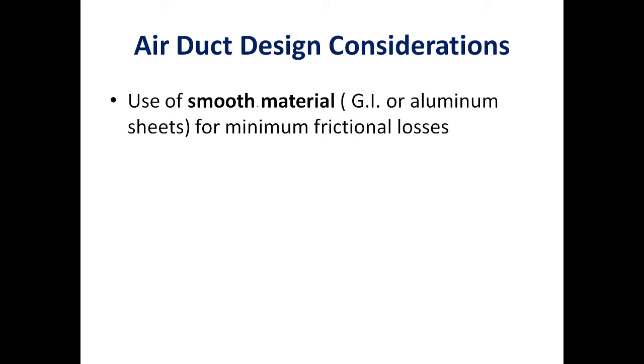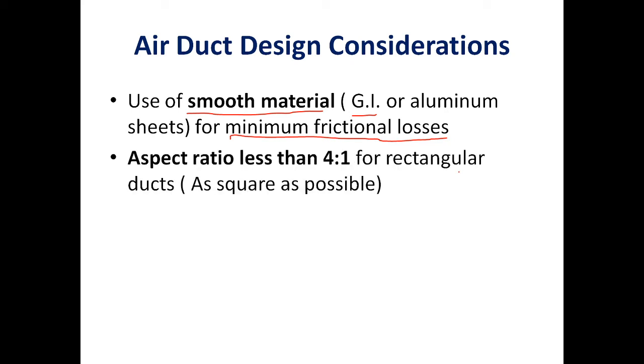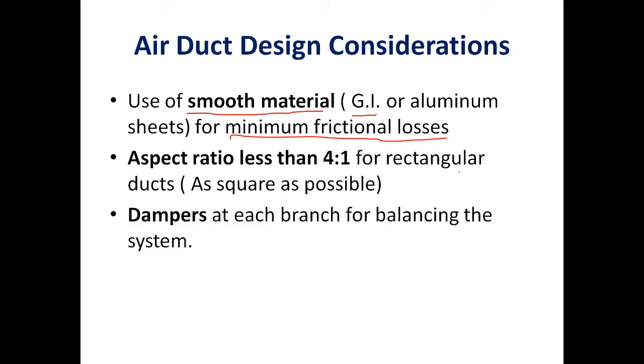Regarding material, the surface finish should be smooth — this is one reason GI and aluminum sheets are preferred for duct construction, as a smooth surface reduces friction losses and hence fan power. The next consideration is aspect ratio, which should be less than 4:1 for rectangular ducts. Dampers are also provided for regulating airflow, directing airflow, and balancing the system pressure of the entire air conditioning system.